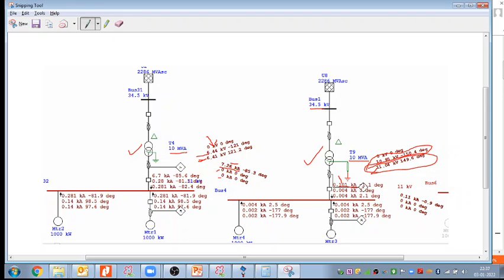The point of concern is if this fault current travels in the core, and the core has insulation, a very thin insulation that we use inside the core. Due to the higher fault current, it will generate heat because we have the coil in the winding. Due to this heat, the core insulation may be damaged.